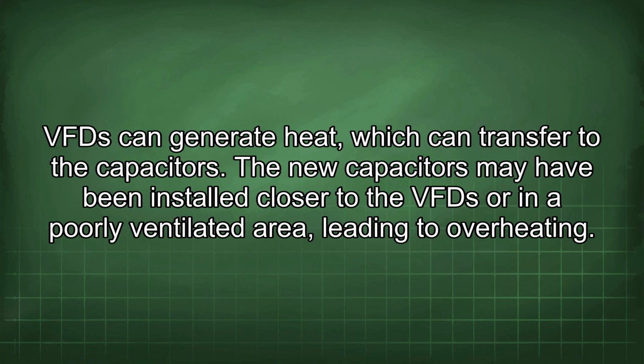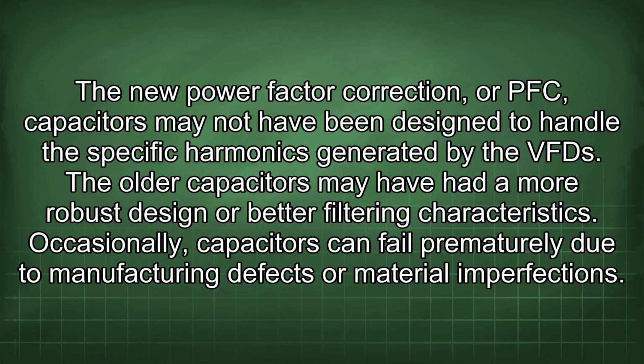VFD can generate heat, which can transfer to the capacitors. The new capacitors may have been installed closer to the VFD or in a poorly ventilated area, leading to overheating. The new power factor correction, or PFC, capacitors may not have been designed to handle the specific harmonics generated by the VFD. The older capacitors may have had a more robust design or better filtering characteristics.